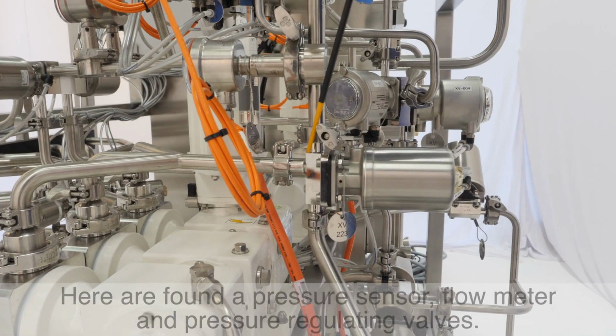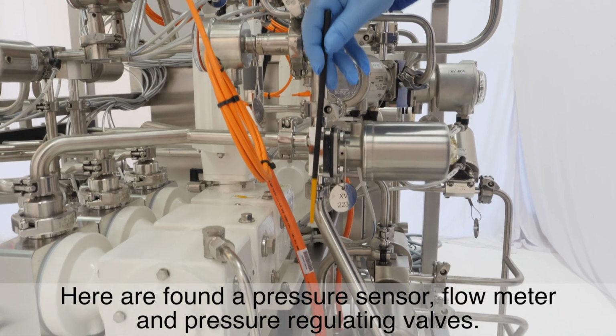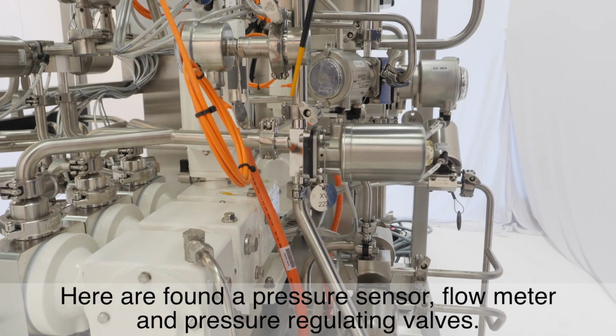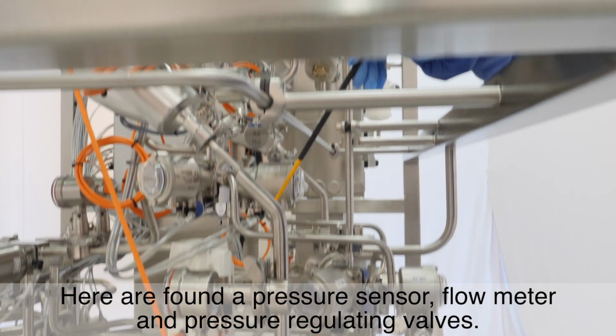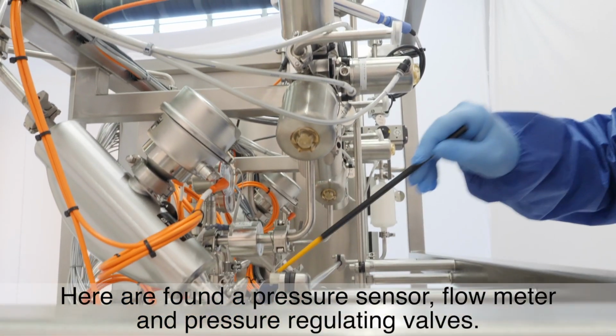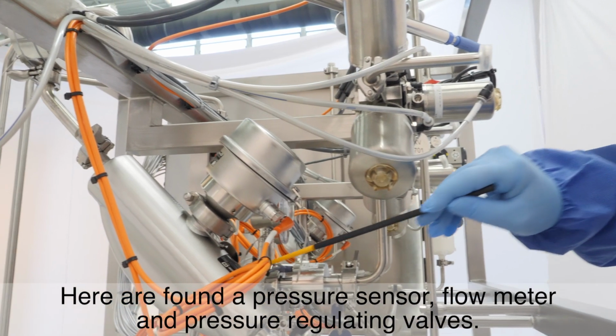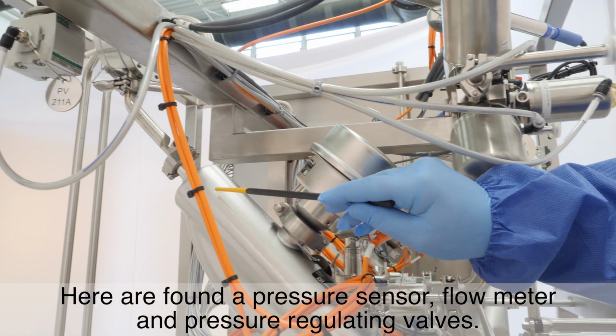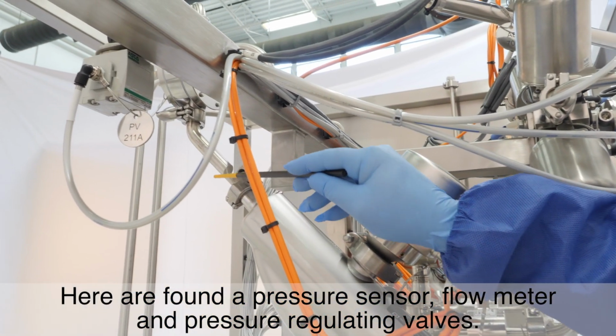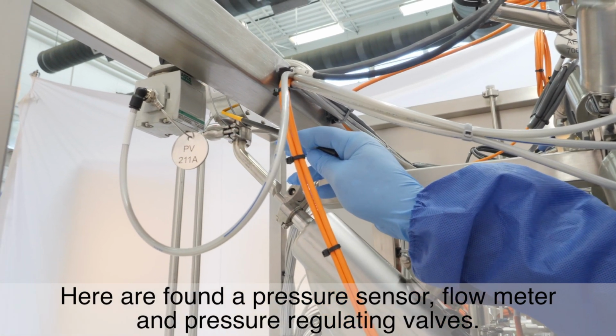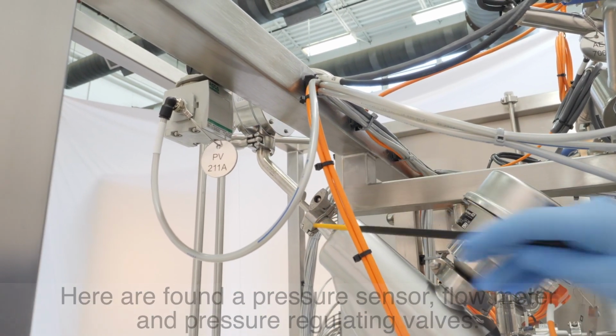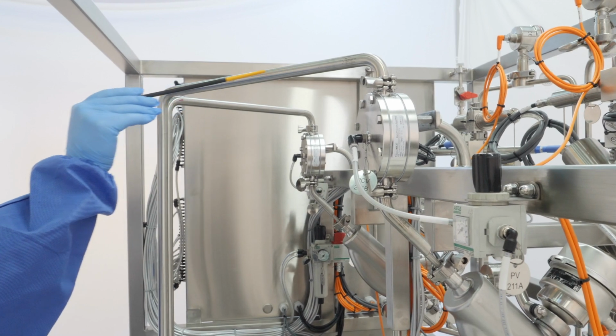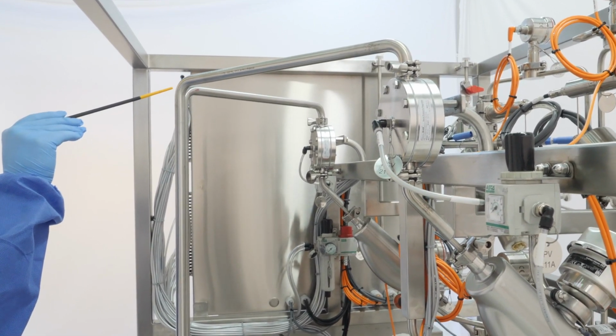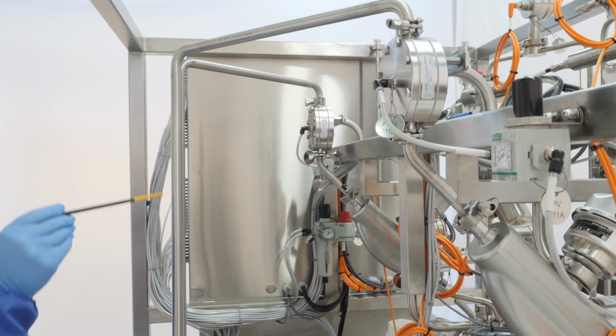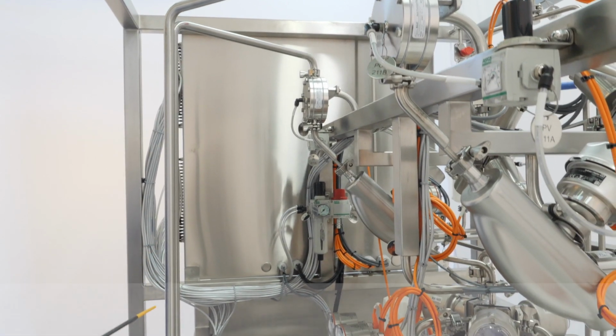On the discharge side of the pumps, there are drain valves which support the priming of the pumps. Also here are pressure sensors. Following are the Coriolis flow meters, which are operated in a control loop with the pumps. Beyond the flow meters, pressure regulating valves are installed. The pressure regulating valves allow reliable pump performance independent of the tank arrangement on the suction side of the pump.